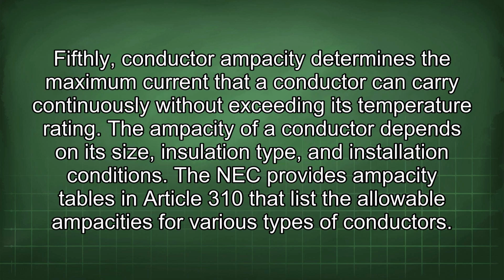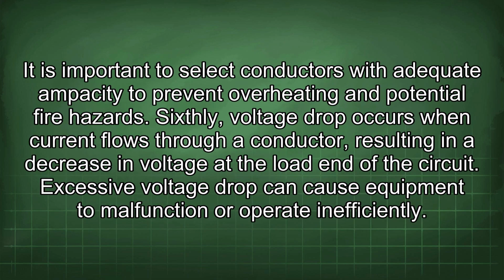Fifthly, conductor ampacity determines the maximum current that a conductor can carry continuously without exceeding its temperature rating. The ampacity of a conductor depends on its size, insulation type, and installation conditions. The NEC provides ampacity tables in Article 310 that list the allowable ampacities for various types of conductors. It is important to select conductors with adequate ampacity to prevent overheating and potential fire hazards.